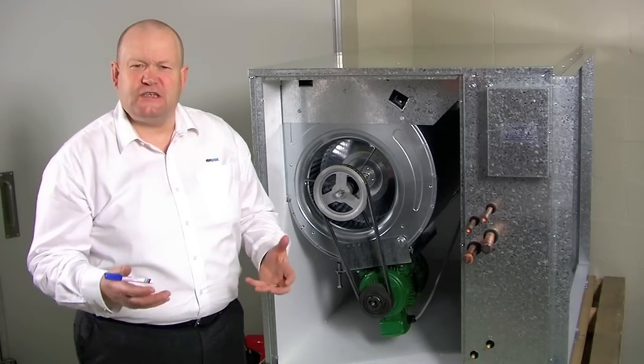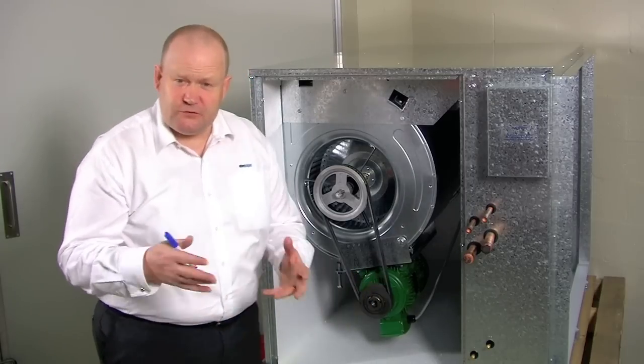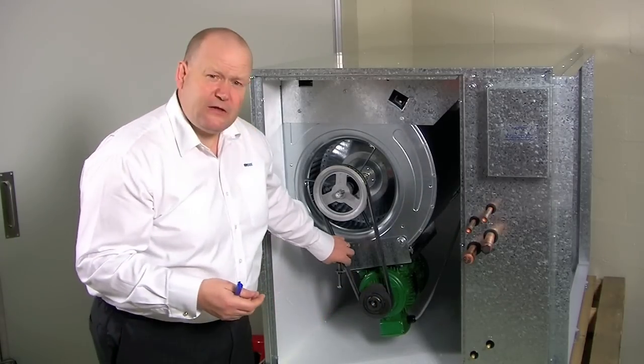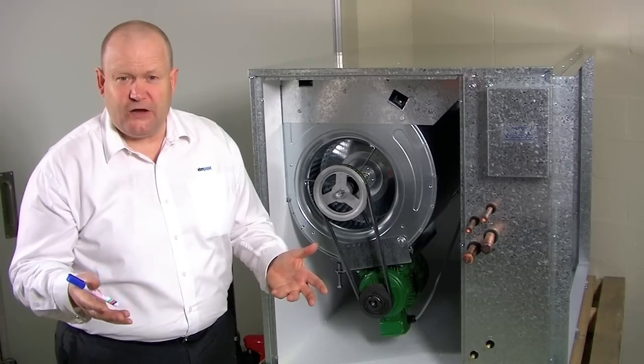So let's look at the efficiency losses that are typical in this type of product. First of all there's the motor, and I've talked about that previously: 15% losses. Then there's the belts. Between 7% to 15% losses during their lifetime is typical.